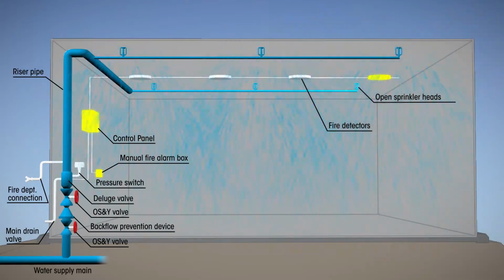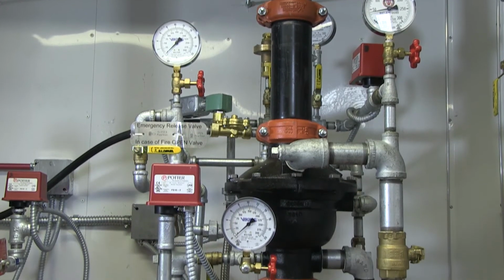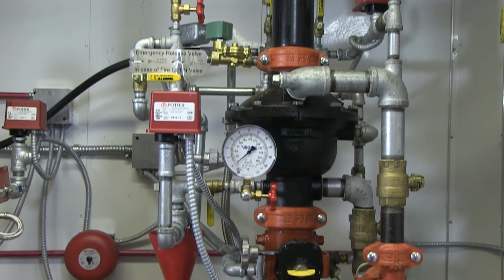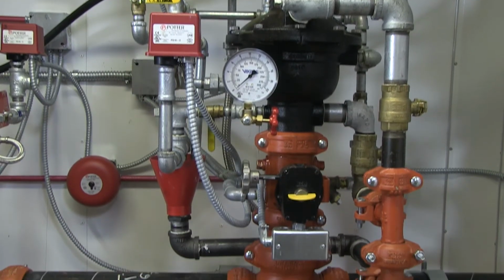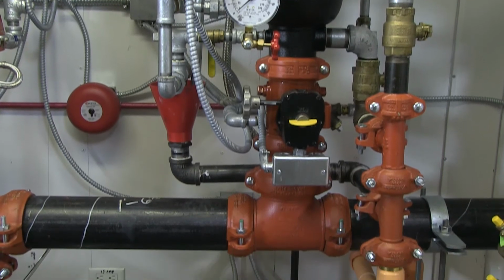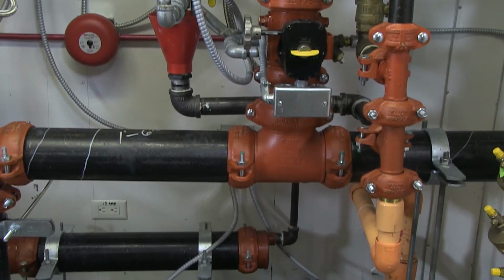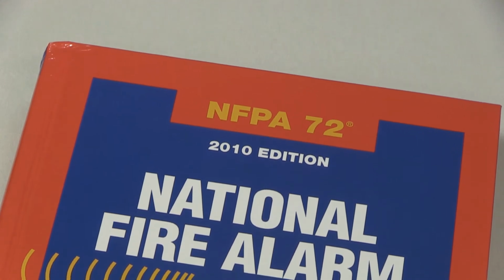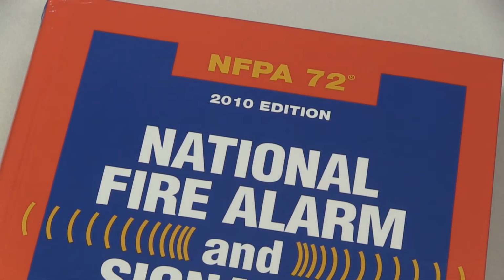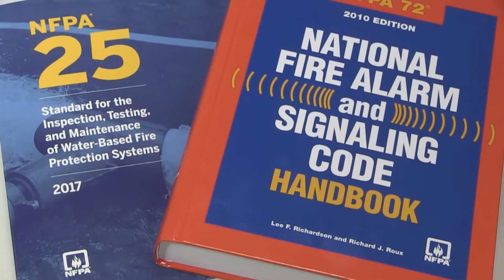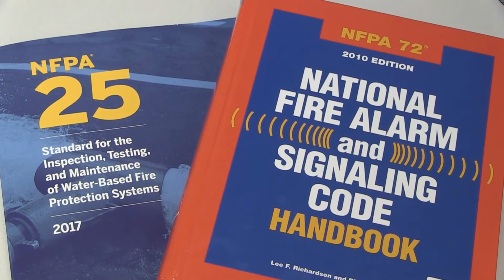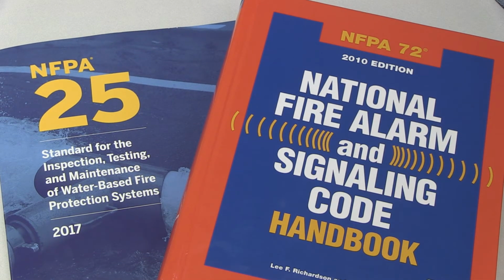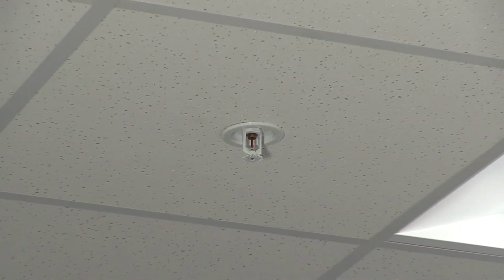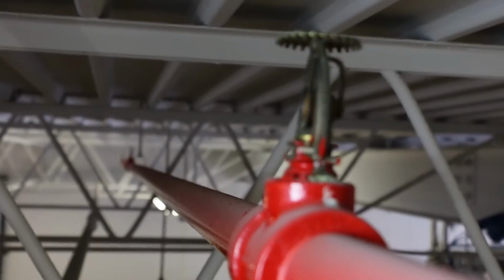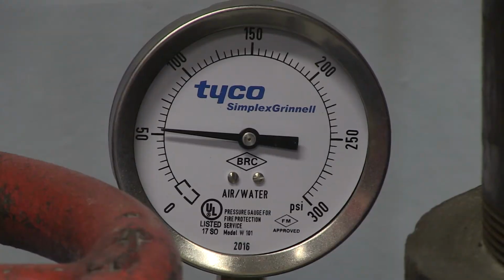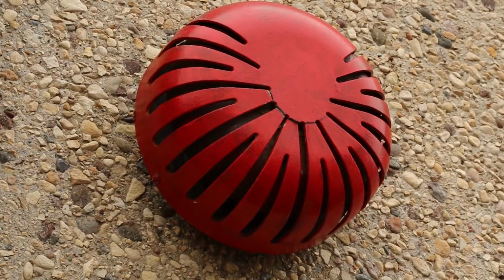Note, in pre-action and deluge systems, the ITM of the electrical components of the automatic fire detection equipment used to activate the sprinkler system are not addressed by NFPA 25, but instead addressed within the NFPA 72 standard. In those cases, the NFPA 25 and NFPA 72 standards must be coordinated to ensure the system operates as intended. Components that must be inspected include sprinklers, piping, hangers and braces, pressure gauges, and alarm devices.